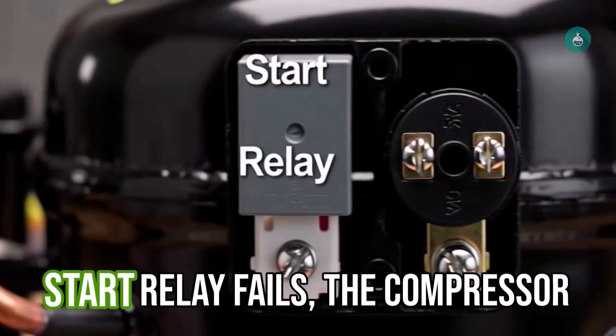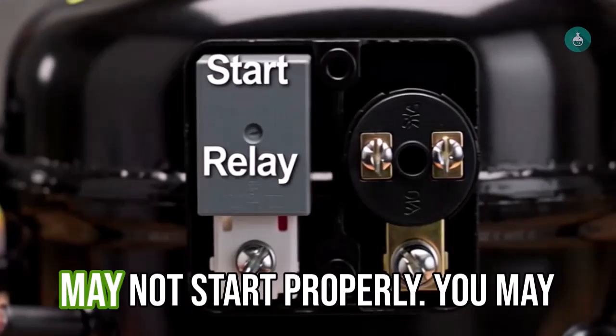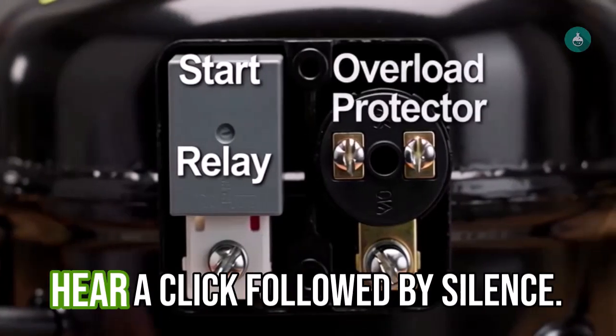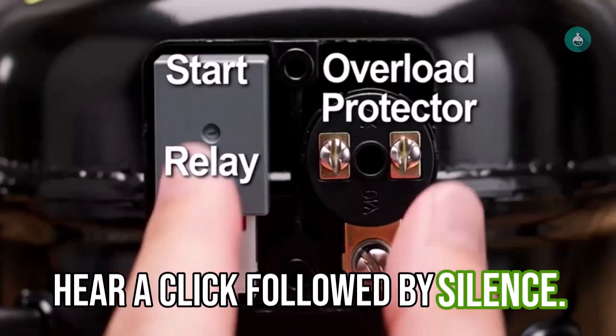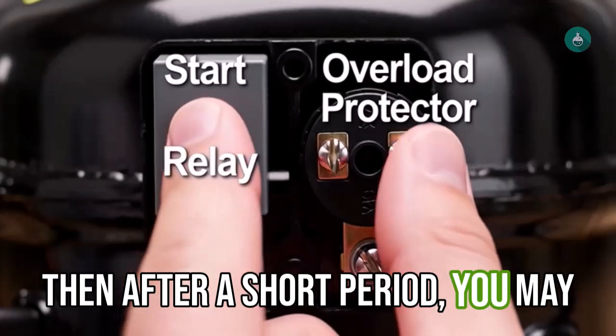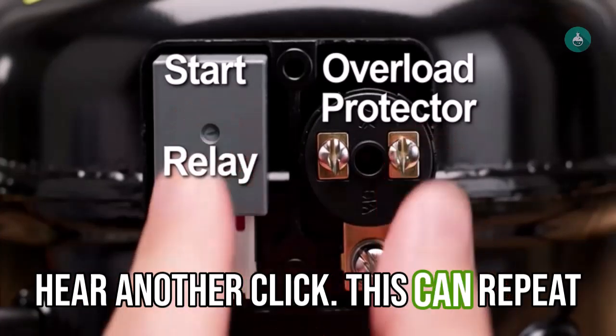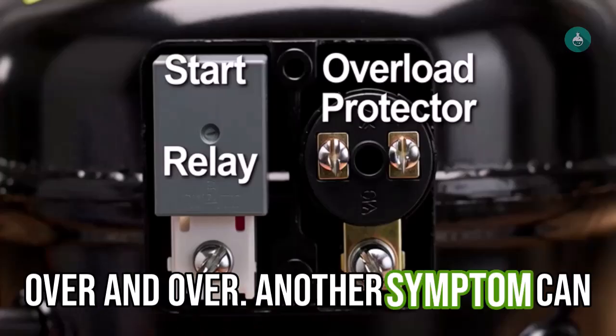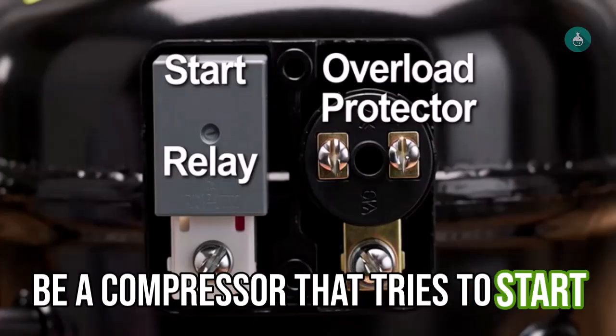If the start relay fails, the compressor may not start properly. You may hear a click followed by silence. Then, after a short period, you may hear another click. This can repeat over and over. Another symptom can be a compressor that tries to start, hums for a few seconds, and then shuts off.